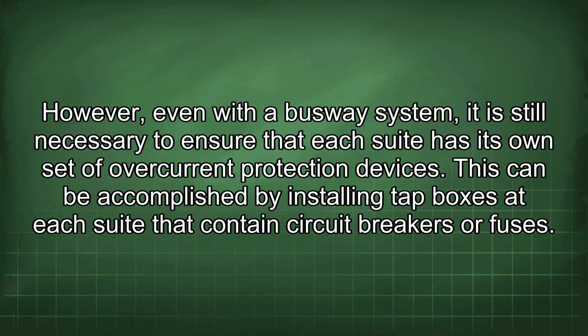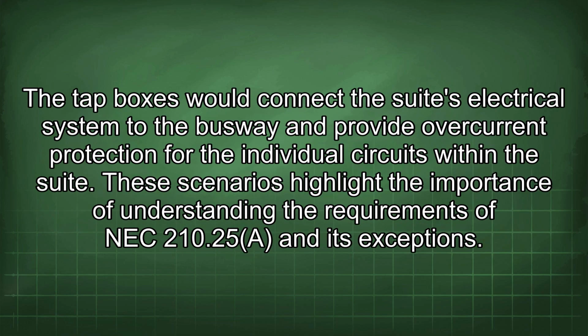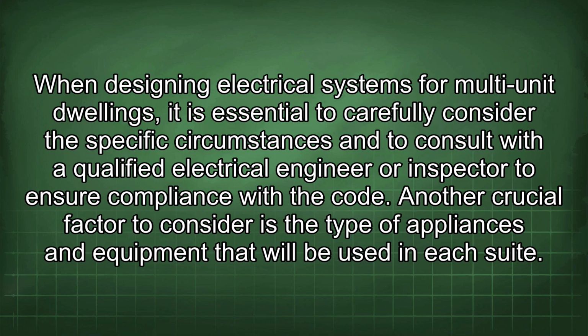However, even with the busway system, it is still necessary to ensure that each suite has its own set of overcurrent protection devices. This can be accomplished by installing tap boxes at each suite that contain circuit breakers or fuses. The tap boxes would connect the suite's electrical system to the busway and provide overcurrent protection for the individual circuits within the suite. These scenarios highlight the importance of understanding the requirements of NEC 210.25 and its exceptions. When designing electrical systems for multi-unit dwellings, it is essential to carefully consider the specific circumstances and to consult with a qualified electrical engineer or inspector to ensure compliance with the code.